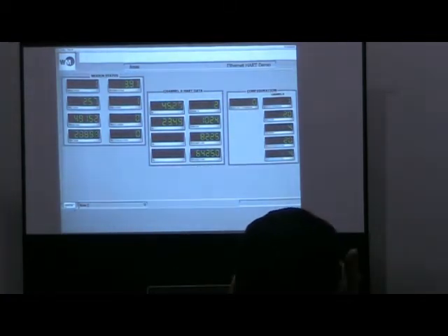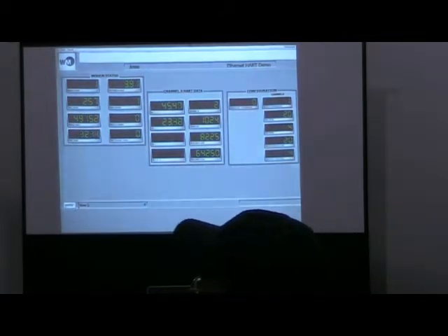So this is a benefit, for example, in permit critical applications. Earlier you referred to a maintenance mode. If a guy forgot to put it back in, you can see the live data, or if it's saturated. Right now you're 50 degrees, but realistically you're 45 degrees, and it looks like you're climbing again because you took the ice off. Put it back on, before we have water running over there.